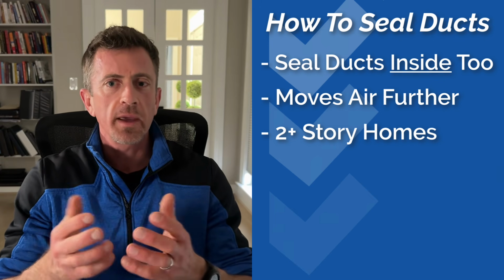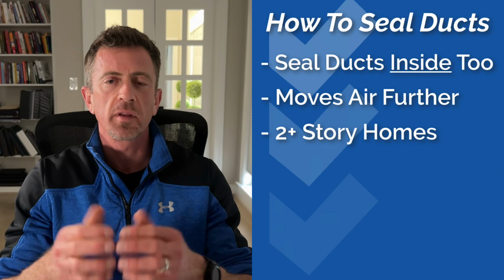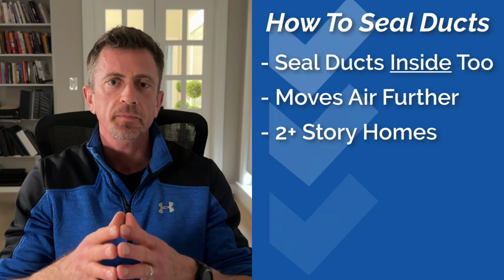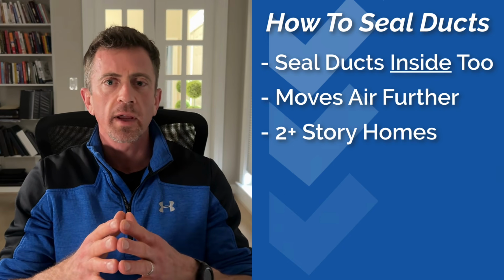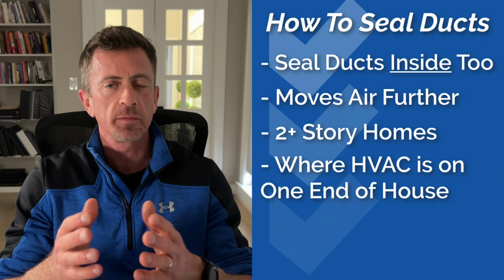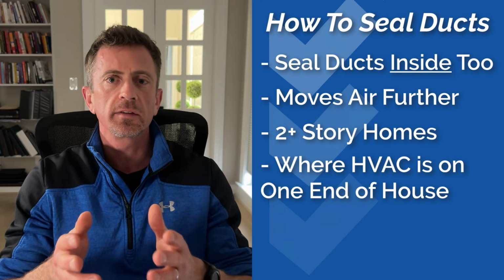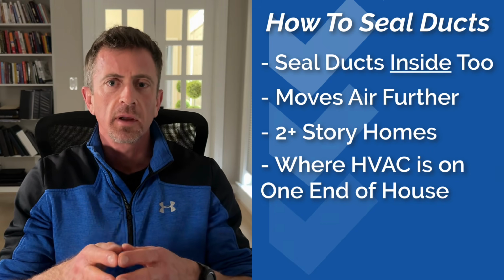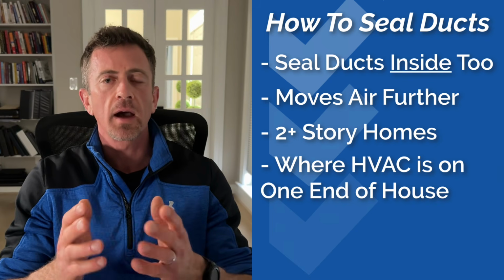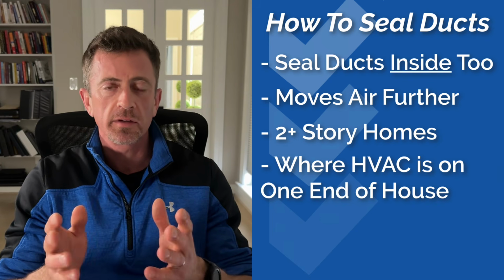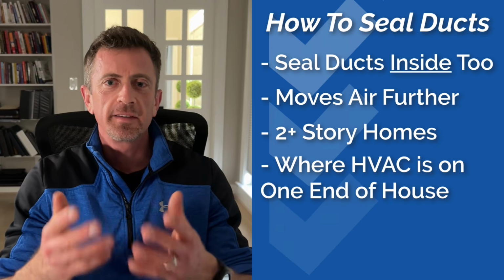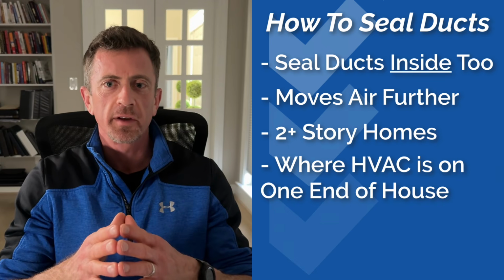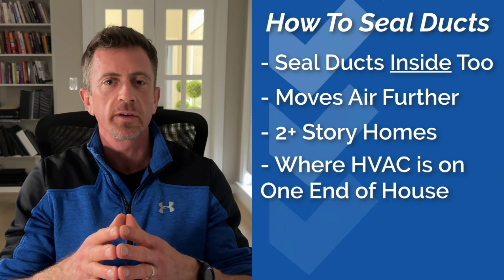The air often doesn't make its way to the top floors as well as it does to the basement and the first floor. It's also an issue in ranch-style homes where the HVAC system is on one end and there's a long distance to the opposite end of the house. That far side usually ends up being hotter or colder than the rest of the house year-round. Sealing ductwork and insulating the supply side of the duct system can really help reduce those temperature differences.